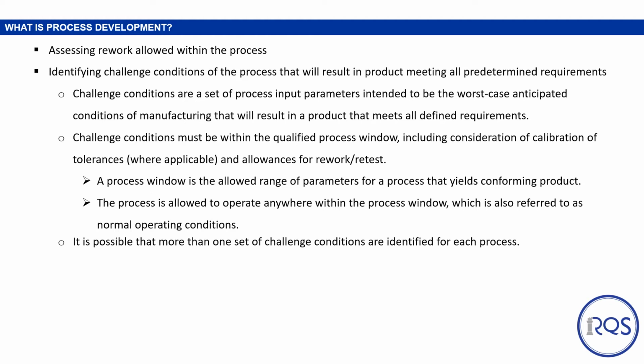When we assess rework allowed, we want to get a better understanding of any potential adverse events that may occur by simply redoing the process. It may be something that's impactful to the product itself, or it could also be something that results in hazardous situations for users. Then again, we want to identify challenge conditions of the process that will result in the product meeting all predetermined requirements. Challenge conditions are a set of process input parameters that are intended to be the worst-case anticipated conditions of manufacturing that will still result in the product meeting all defined requirements. The worst case is the very lowest of settings, or the very highest of settings, that we can run product at, and it still ends up meeting the defined requirements.